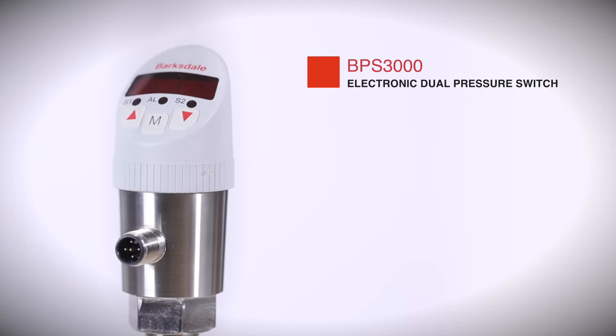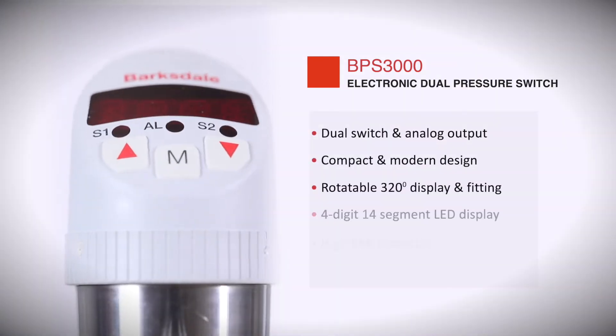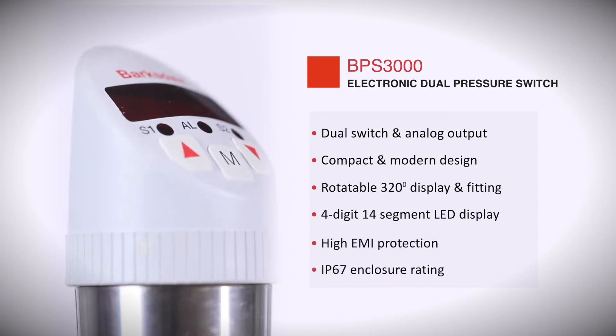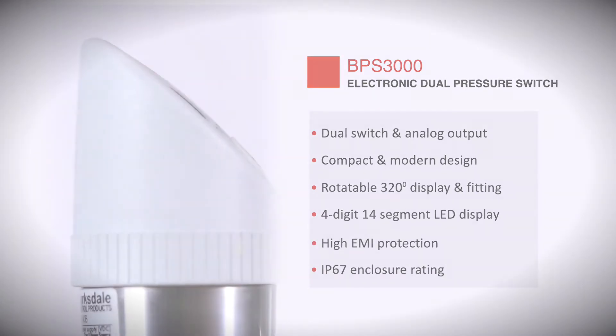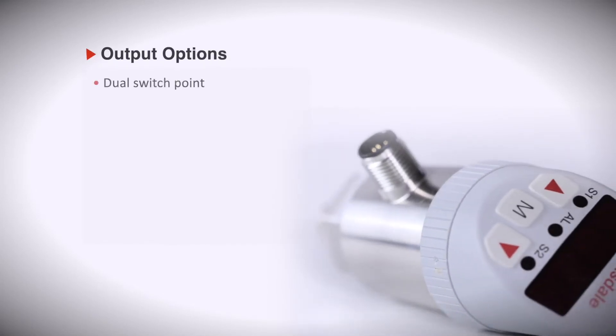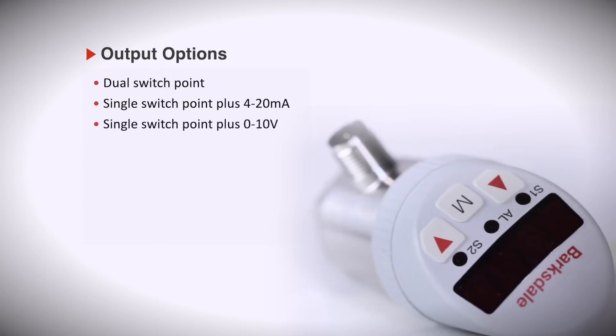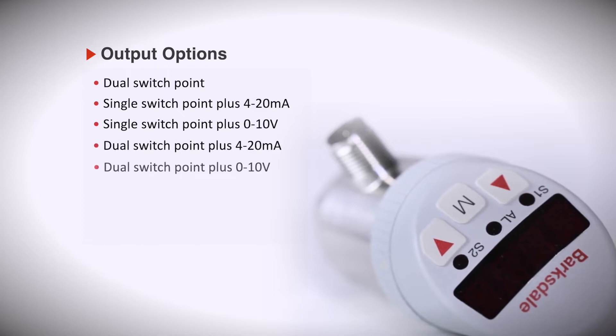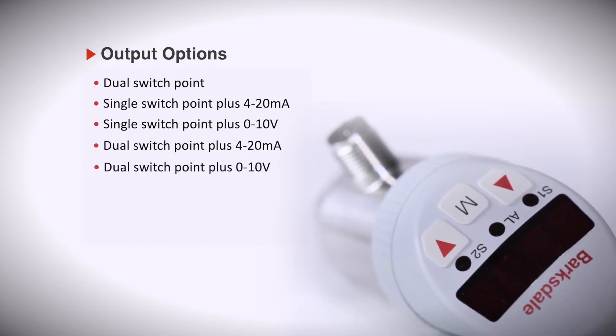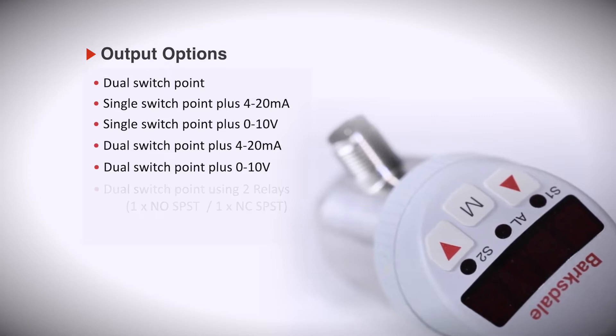The model BPS 3000 electronic dual pressure switch comes with the functionality of a switch, transducer, and display in just one instrument. The BPS 3000 offers various output options: single or dual switching output along with optional 0 to 10 volt DC or 4 to 20 milliampere analog output signal, enabling precise continuous measurement and sensing.